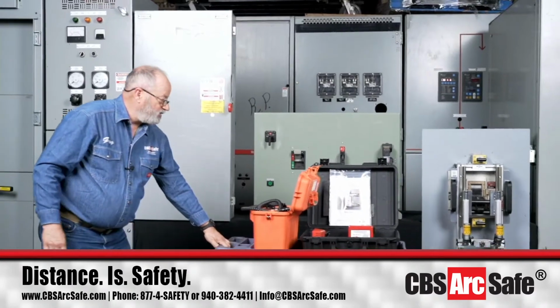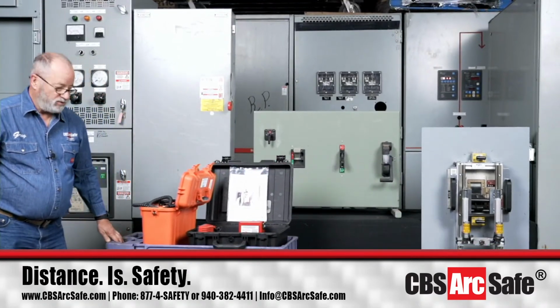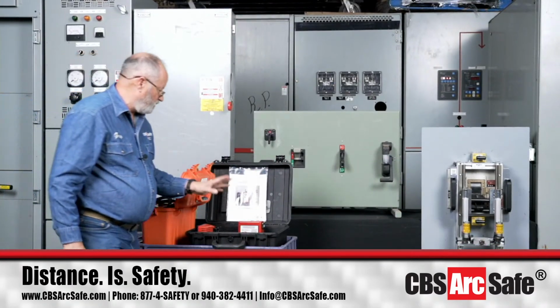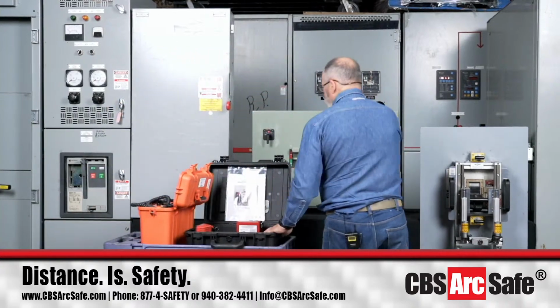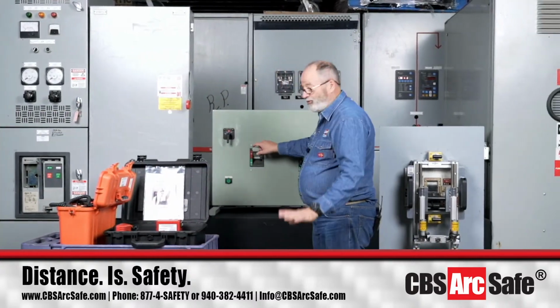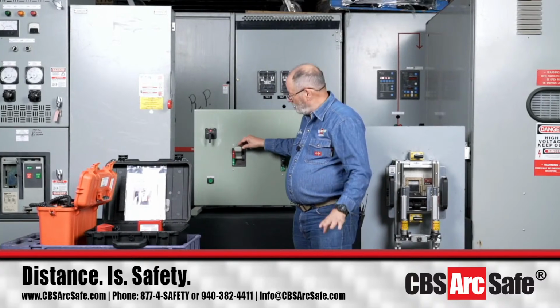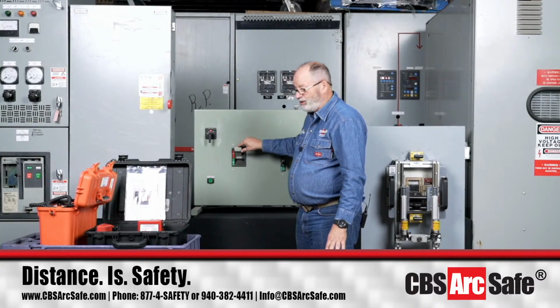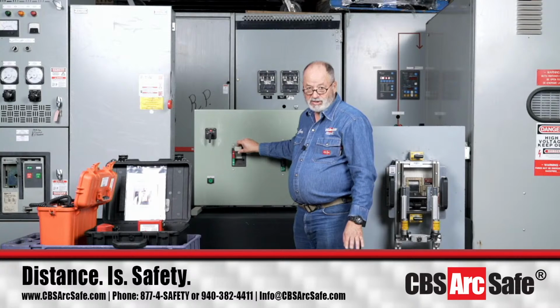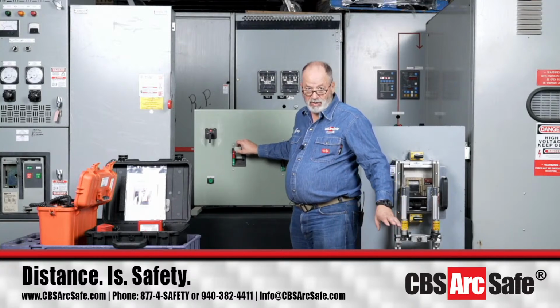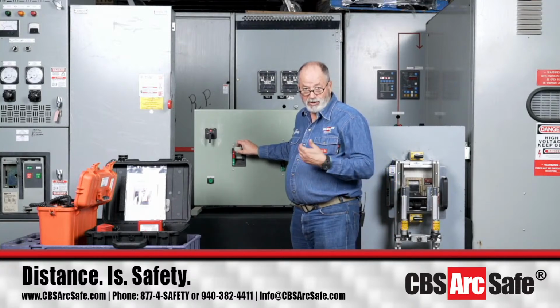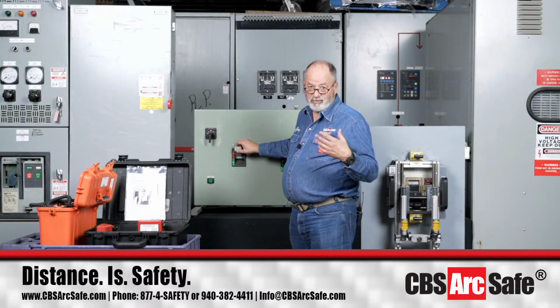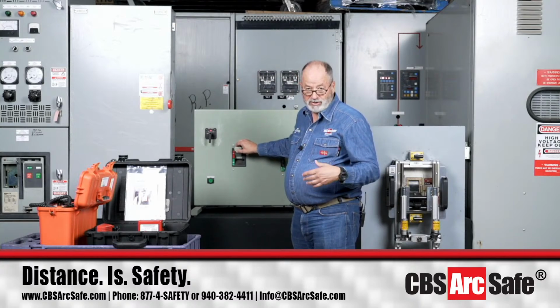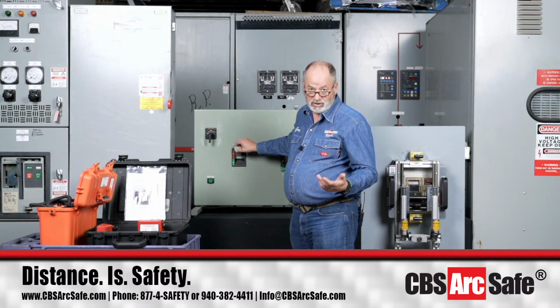All right, the next thing we're going to do is use the CHL1. One thing to note: before I put this on and start to operate it, you'll notice it's spring-loaded to the up position. That's just because this is a basic handle with no circuit breaker behind it, no mechanism. So each time we perform a close or open operation, it's always going to return to the up position.